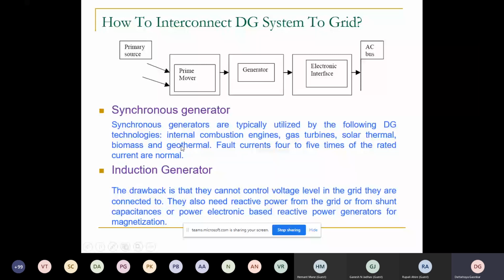Of course, induction generators do not have reactive power controllability. You require a bank of capacitors, or maybe STATCOM devices, to supply the reactive power.